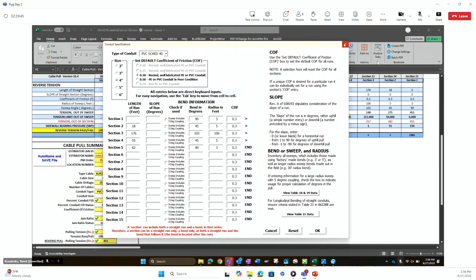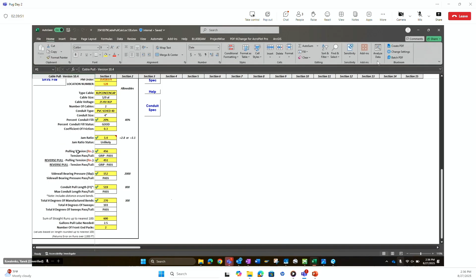We would put it into our Excel spreadsheet—it's a 9-foot section, then it's got a 45, then we'd measure another section, another 45, and build out our cable pulling, which at the end would spit out the result of the tension, preferred pulling direction, and reverse pulling direction. We would then copy this data and put it into our tables.